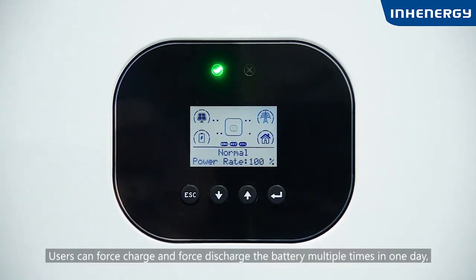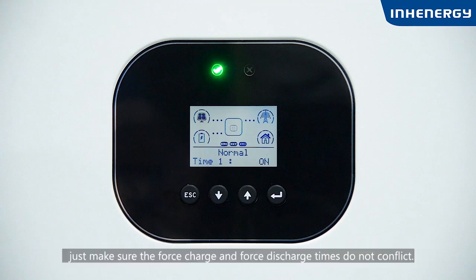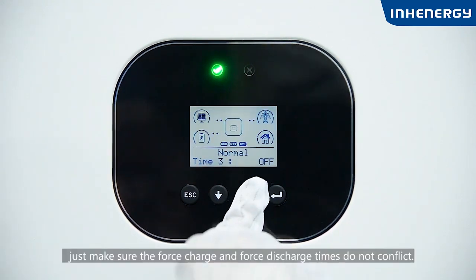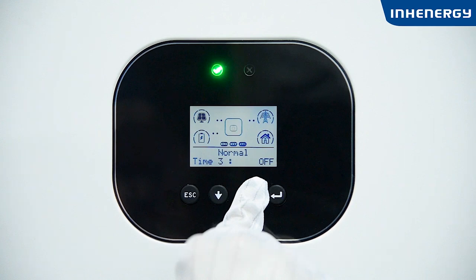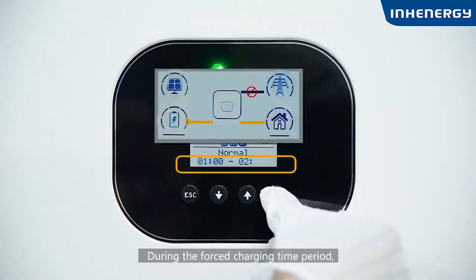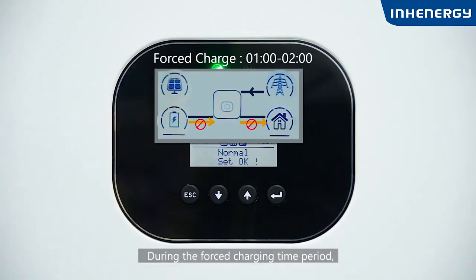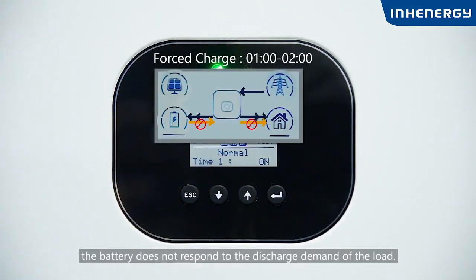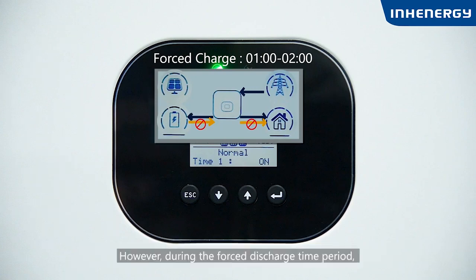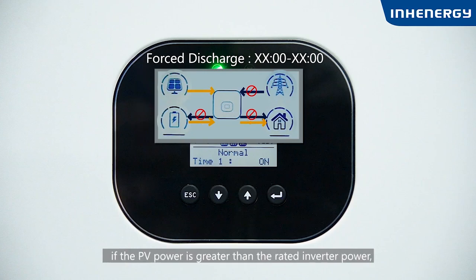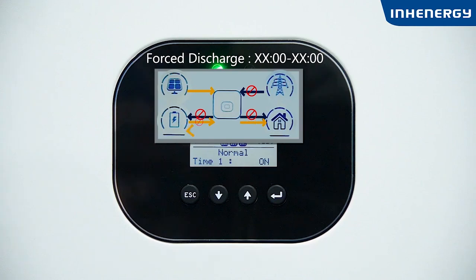Users can force charge and force discharge the battery multiple times in one day. Just make sure the forced charge and the forced discharge times do not conflict. During the forced charging time period, the battery does not respond to the discharge demand of the load. However, during the forced discharge time period, if the PV power is greater than the rated inverter power, the excess energy of the PV automatically charges the battery.